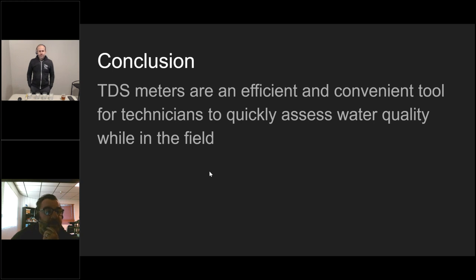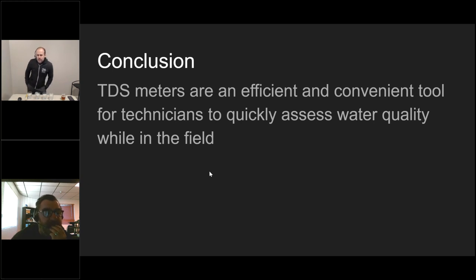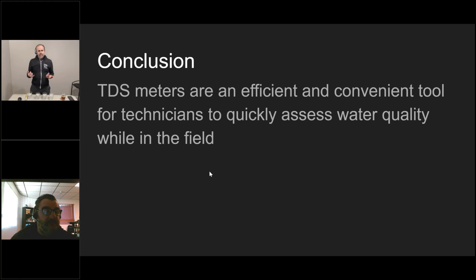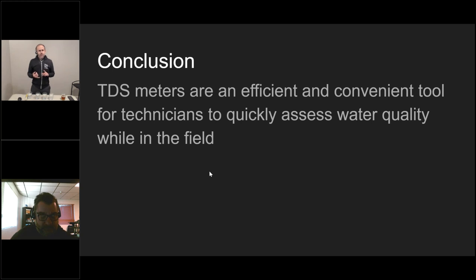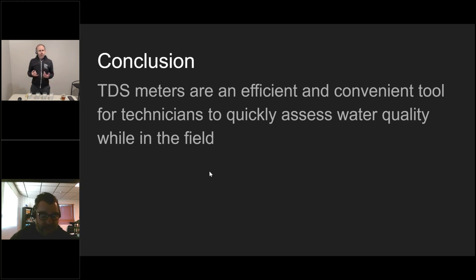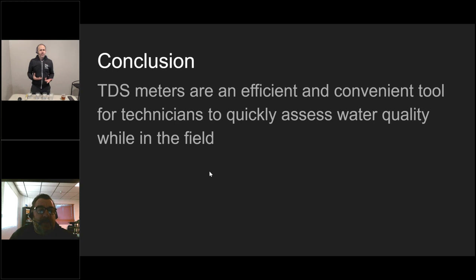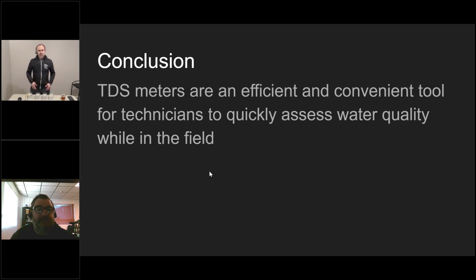What kits do you recommend for checking the different dissolved solids? For field service technicians, I find that drop count titration is relatively inexpensive and fairly accurate. I'm fairly partial to Hach brand kits, like for total hardness, the Hach 5B kits. Like $20 gives you a hundred tests, pretty simple to use. I've used other manufacturers' drop count kits and I've used some from the fish store, but I find Hach tends to be the most easiest to understand and it returns numbers and values that are meaningful to us as technicians.